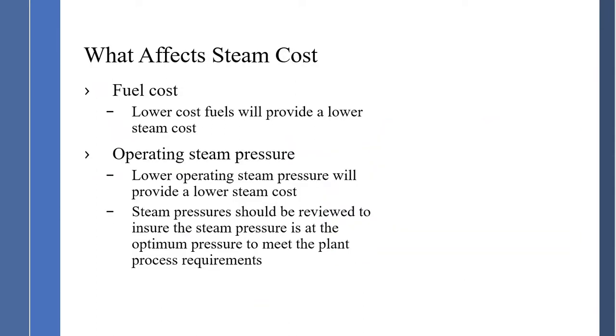What affects steam costs? Fuel costs — lower costs of fuels will provide a lower steam cost, simple as that, depending on how we're purchasing fuel from different sources. Operating steam pressure: lower operating steam pressure will provide a lower steam cost, but caution — steam pressure should be reviewed to ensure it is at the optimal pressure to meet the plant process requirements. Also, the boiler has a design operating pressure and you want to be at that design operating pressure.